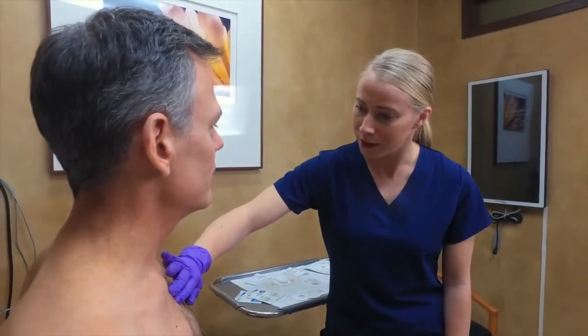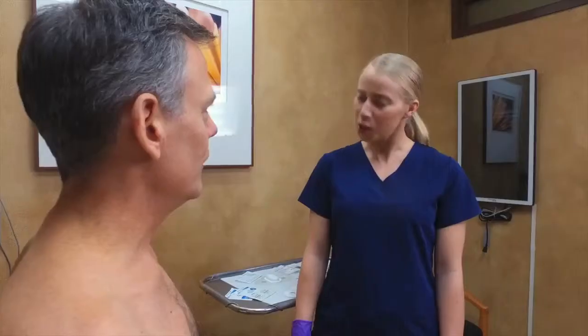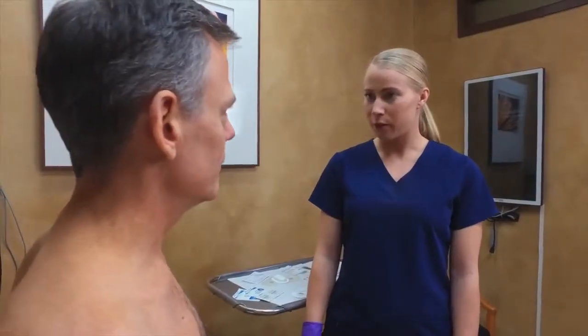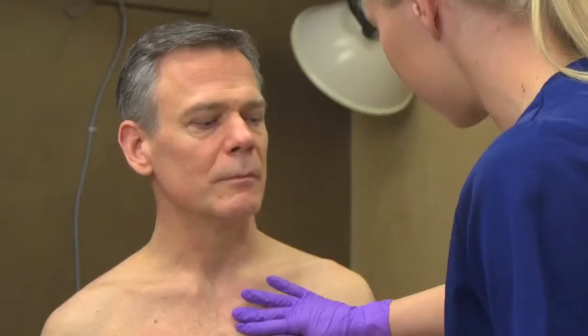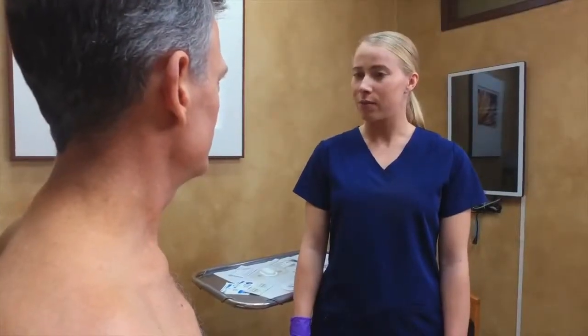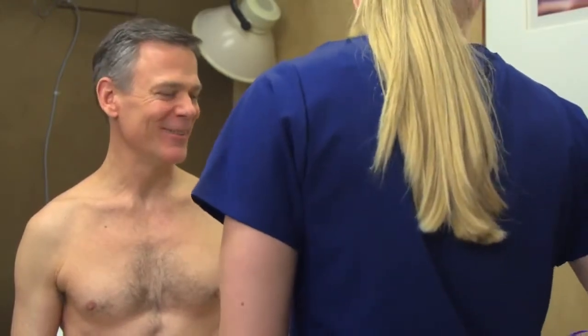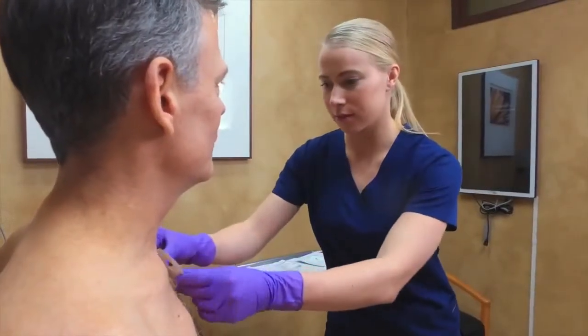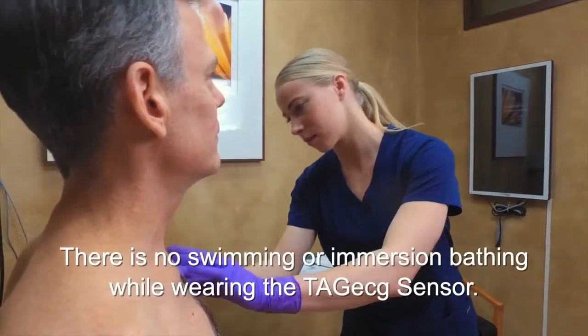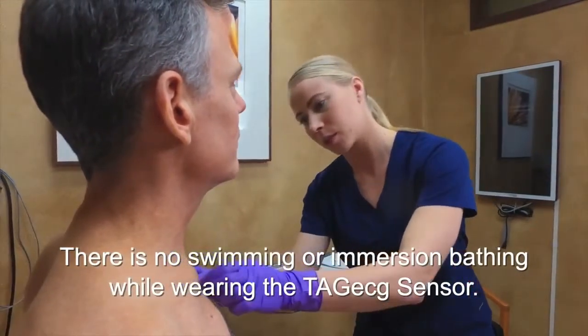Patient education. Verify that the patient has no known allergies or a history of adverse reactions to hydrogel adhesives. Verify that the patient does not have an implantable pacemaker or is scheduled for an MRI procedure. Verify that the patient is not planning to participate in strenuous activity, including at work, that would cause excessive sweating during the sensor wear period. Ensure the patient understands that there is no swimming or immersion bathing while wearing the TAGecg sensor.